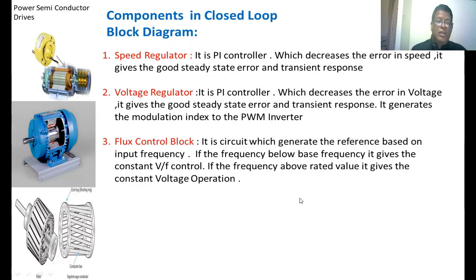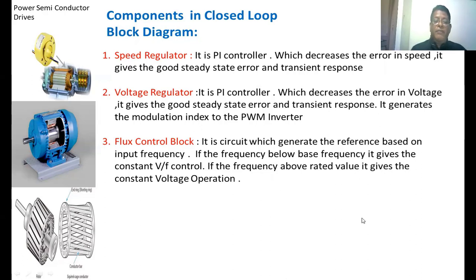Flux control block: It is a circuit which generates a reference voltage based upon the input frequency. The input to the flux control block is the frequency, and the output is the voltage. That voltage is generated based upon the frequency. With the frequency below the base frequency, it gives constant V/F control. With the frequency above the rated value, the voltage applied to the induction motor is kept constant at the rated value.